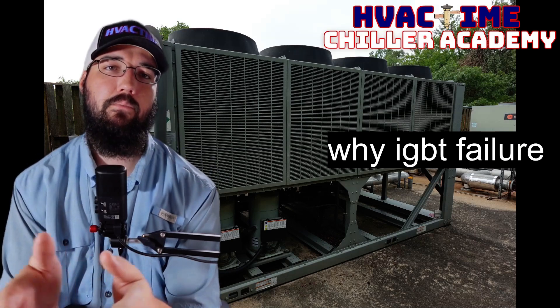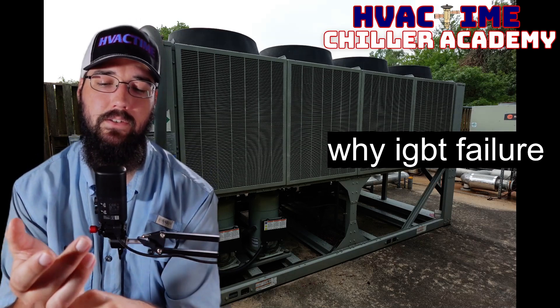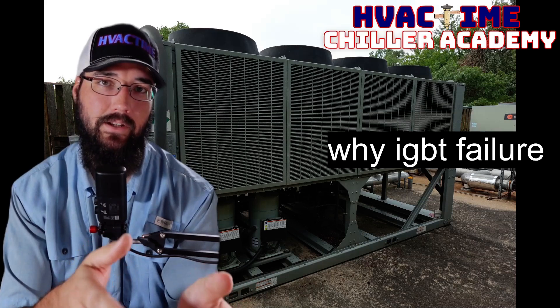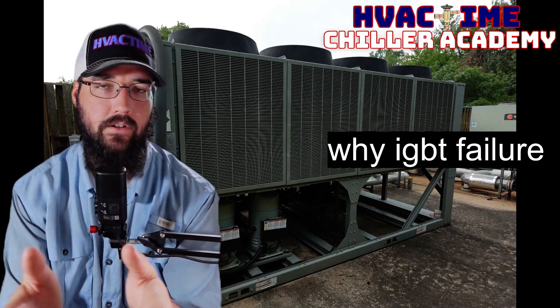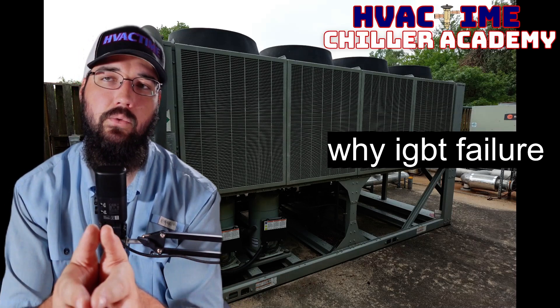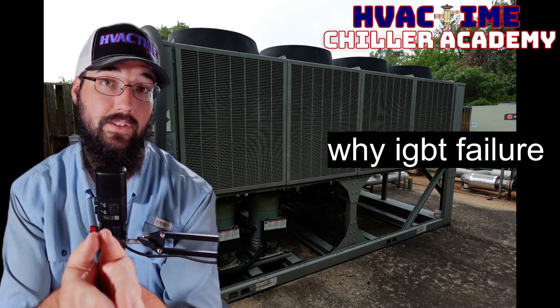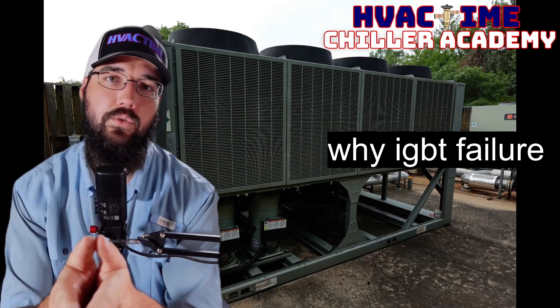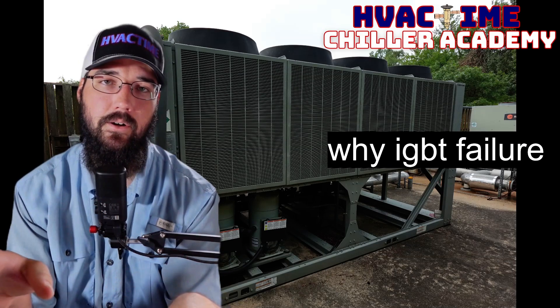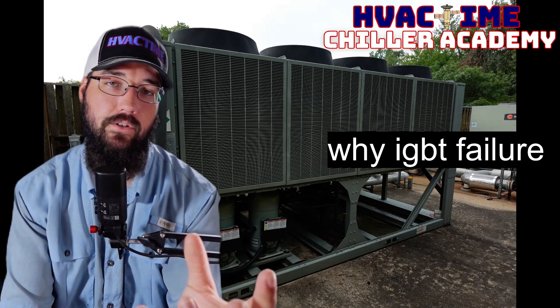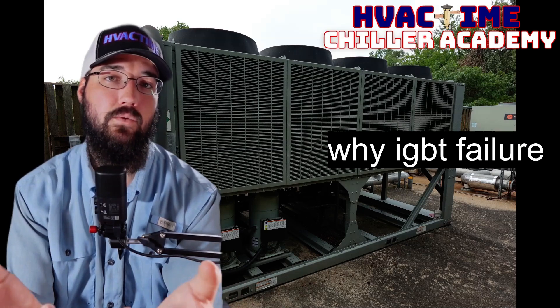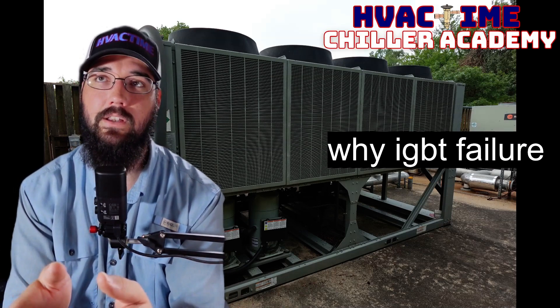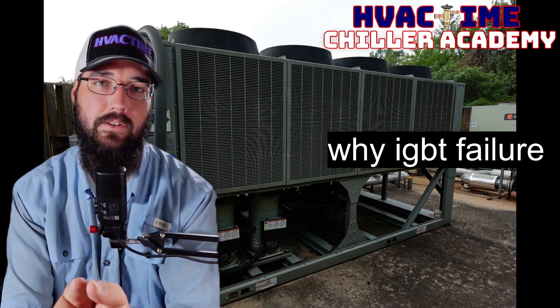Some things I would add to that. Keep in mind, IGBTs can be used as both an inverter and a rectifier. So in a lot of drive technology, like variable speed drives, we have historically used SCRs as silicon controlled rectifiers, hence the rectification. We've used those rectifiers to get our positive and negative DC bus. And so the inverter and rectifier indicate its actual purpose in the system. The IGBT or SCR is the style of component that is being used.